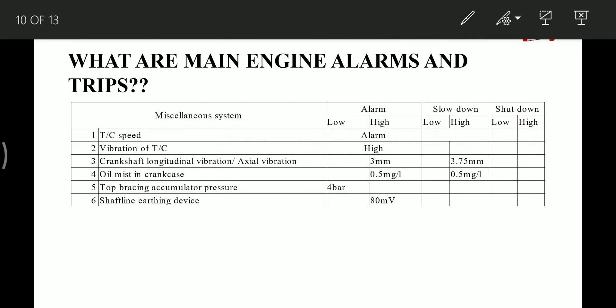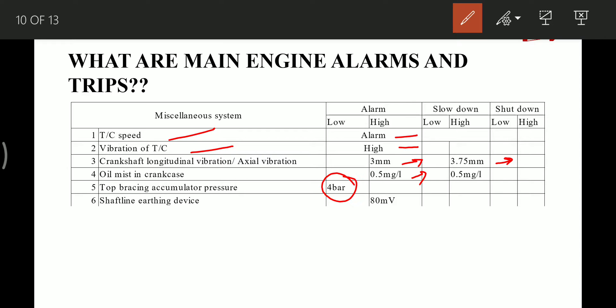Miscellaneous alarms: turbocharger speed — alarm if high or low. Turbocharger vibration — high alarm if value is high. Crankshaft longitudinal/axial vibration — alarm at 3 mm and slowdown at 3.75 mm. Oil mist in crankcase — alarm and slowdown at 0.5 mg/litre. Top bracing accumulator pressure — low pressure alarm at 4 bar or less. Shaft line earthing device — alarm if value exceeds 80 mV.